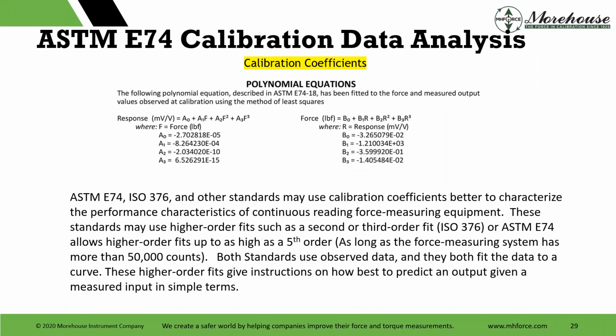So, calibration data coefficients. ASTM E74, ISO 376, and other standards may use calibration coefficients to better characterize the performance of continuous reading force equipment. These standards may use higher order fits, such as second order and third order. That's ISO 376; they only go to third order. ASTM E74 goes as high as fifth order, as long as the force measuring instrument has 50,000 counts or more of resolution. Both standards use observed data, and they both fit the data to a curve. These higher order fits give instructions on how best to predict an output given a measured input, in simple terms.